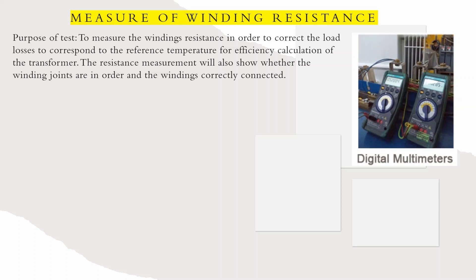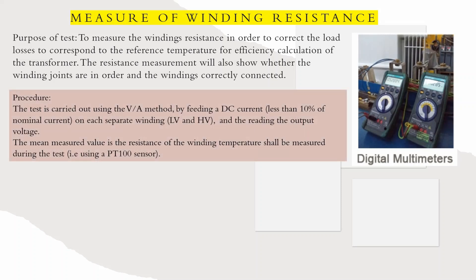There are a lot of digital meters and multimeters available. The purpose of this test is to measure the winding resistance in order to correct the load losses, corresponding to the reference temperature for efficiency calculations of the transformer. The procedure is carried out using the volt-ampere method by feeding DC current less than 10% of nominal current on each separate winding.